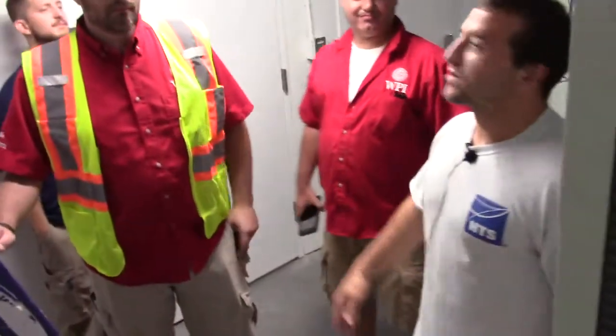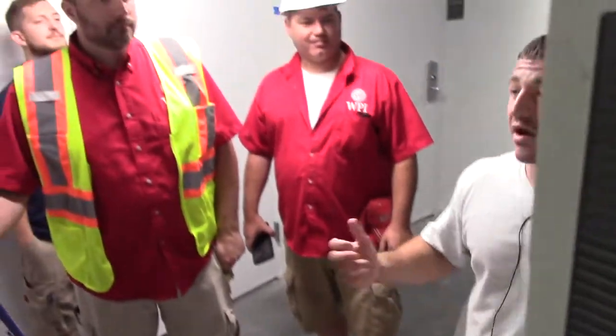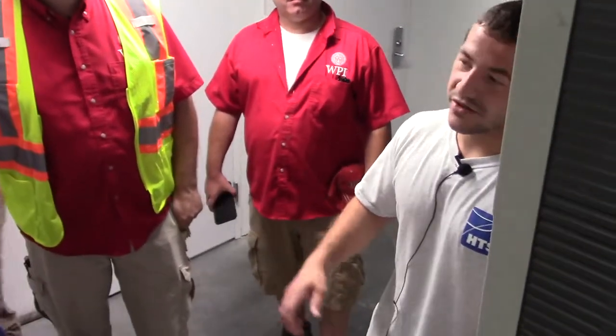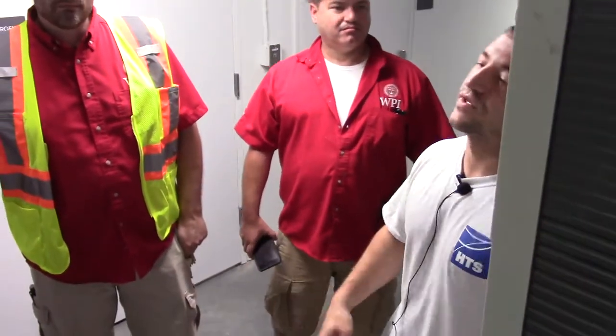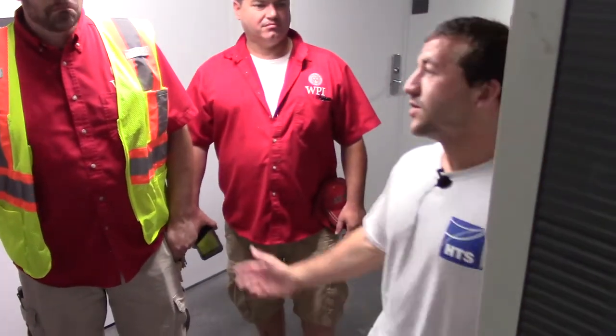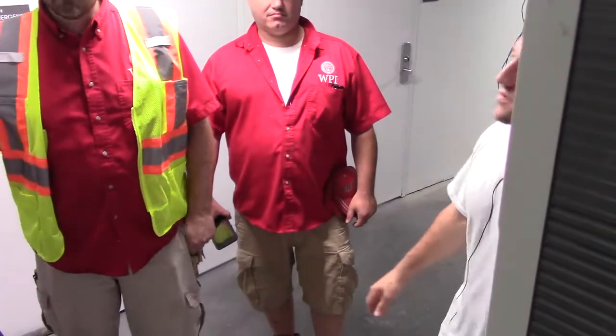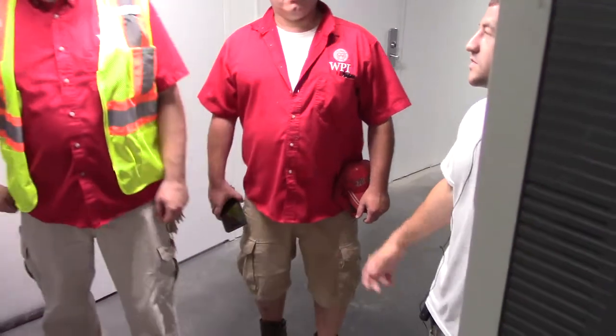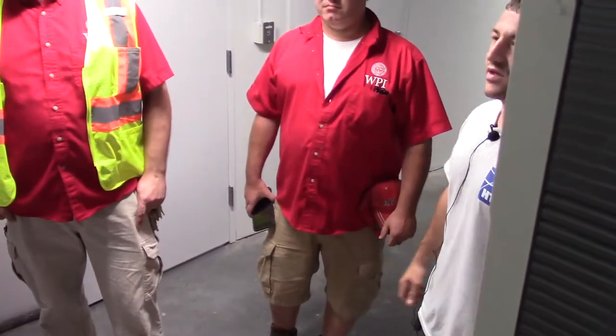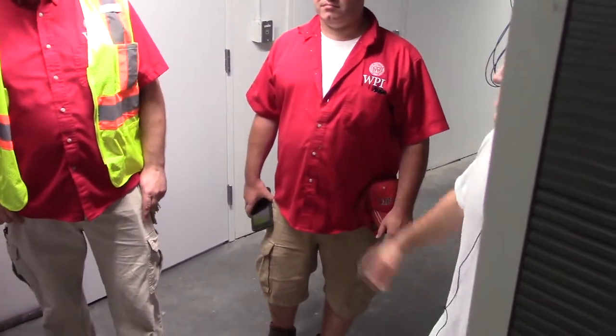Do you have any other questions? And then every so often, once a year or something like that, do a full shutdown and just pop open the covers on the VFDs, tighten any electrical connections, and make sure nothing's getting loose and going to fall out or anything like that. But other than that, that's pretty much it. Questions? You good? Pretty easy, self-explanatory.